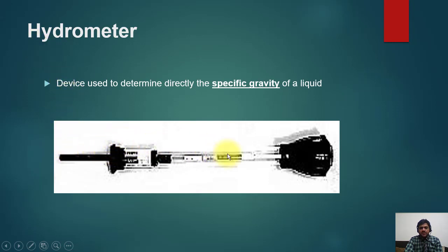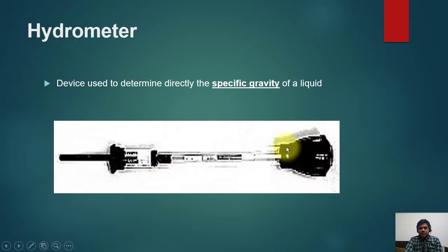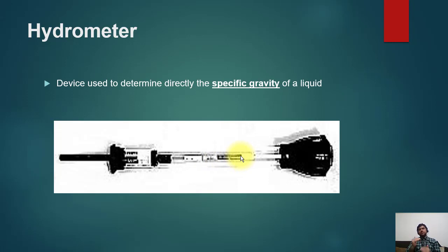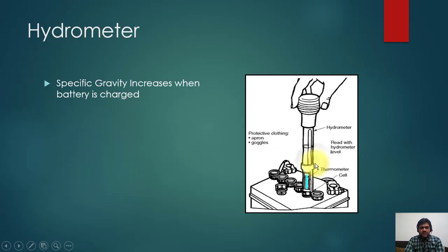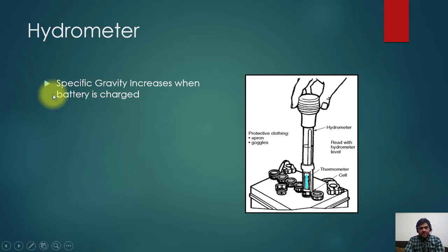To measure the specific gravity of the electrolyte, you use a device called a hydrometer. You press the black rubber bulb to draw the electrolyte into the hydrometer. A float inside will float in the electrolyte, and you read the position marking to measure the specific gravity. For lead-acid batteries specifically, the specific gravity increases when the battery is charged. For other types of batteries, specific gravity does not change significantly.